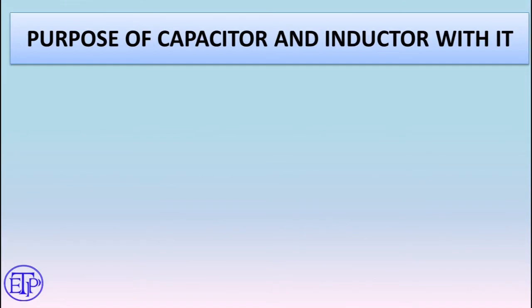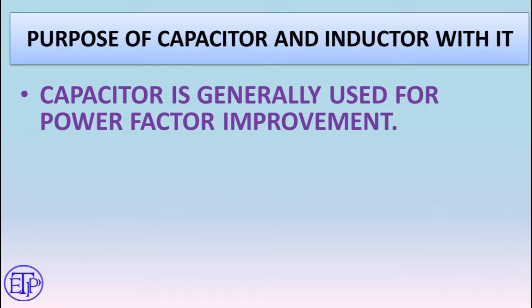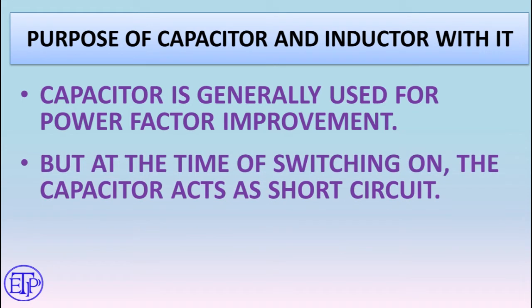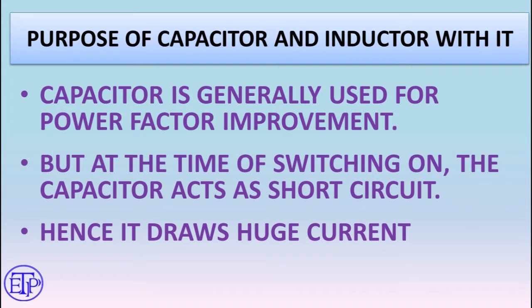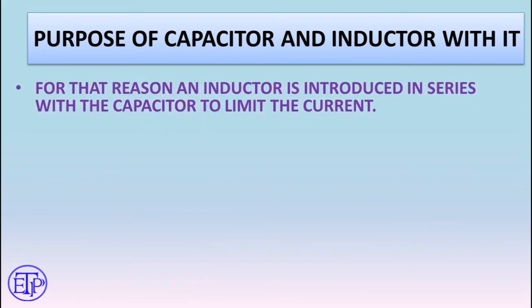Purpose of capacitor and inductor together: We know that a capacitor is generally used for power factor improvement. However, at the time of switching on the capacitor, it acts as a short circuit and draws a huge current. The capacitor opposes sudden change of voltage, so whenever you switch on a capacitor, it acts like it has no internal voltage — drawing huge current to get charged — and gradually the voltage builds up and the current reduces. But this huge initial current may damage the capacitor.